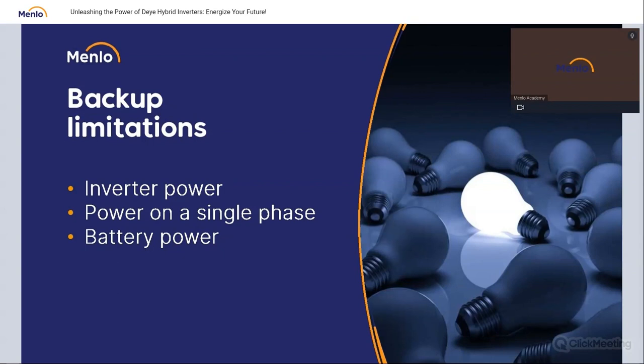One of our first sold installations, it was a hybrid installation a few years ago. We had that situation. That client was so happy, so excited that he has a hybrid installation, has batteries, has a PV system, and so on. So he cut himself from the grid. He did it on purpose. He knew what he was doing because he was so happy that he could use his own energy from the batteries. But during the night, this guy turned on his electric sauna, which takes 11 kilowatts, and the system collapsed. And he says, why? It's supposed to work. But he didn't mention to the installer that this is the way he will use his installation during the night in off-grid mode.